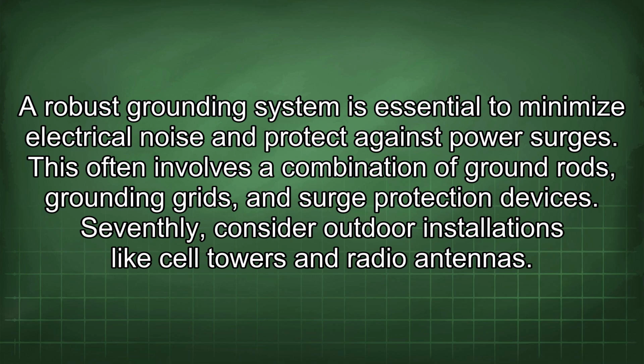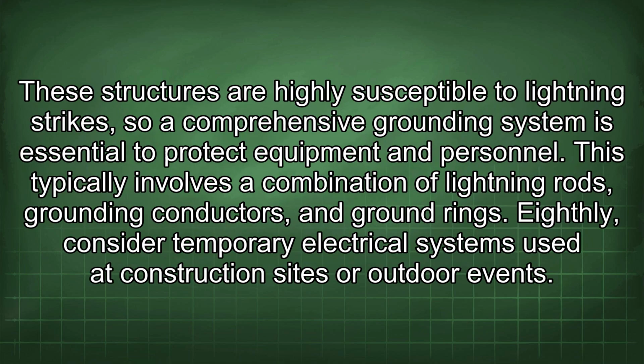Seventhly, consider outdoor installations like cell towers and radio antennas. These structures are highly susceptible to lightning strikes, so a comprehensive grounding system is essential to protect equipment and personnel. This typically involves a combination of lightning rods, grounding conductors, and ground rings.